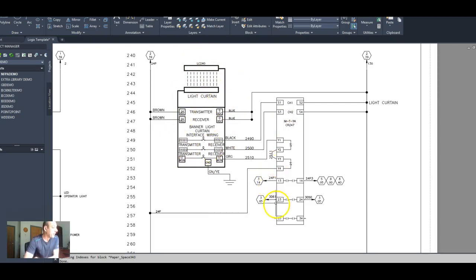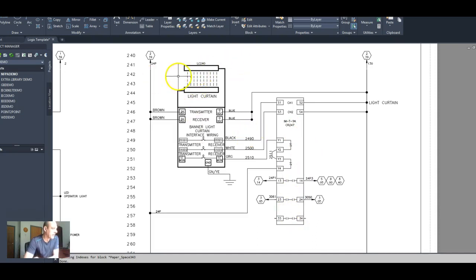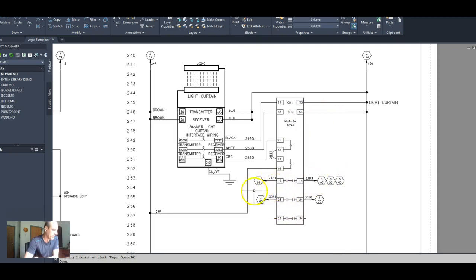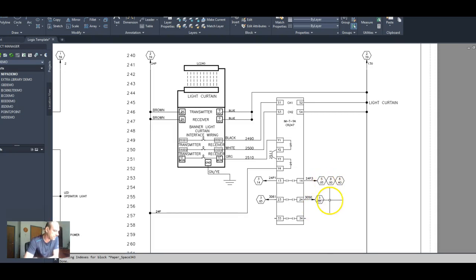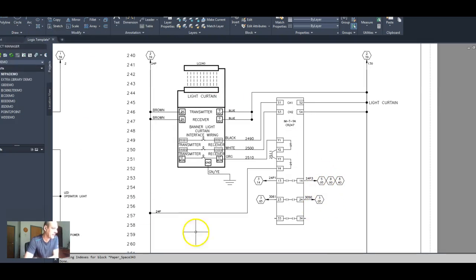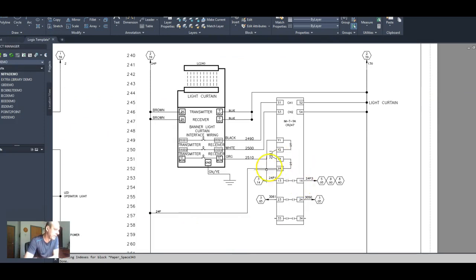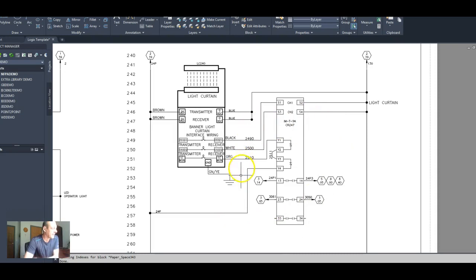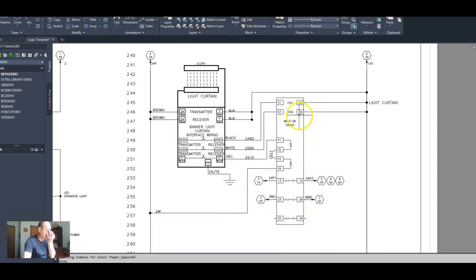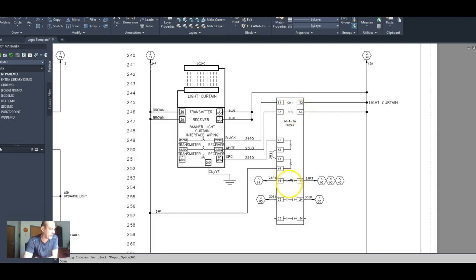We also have a safety relay right here. So if the light curtain gets interrupted, we drop our power out and then we prevent power from going to any other part of our machine. So for example, our 505. If this is energized, remember this print is in a de-energized state. So these are open when these two circuits are energized, these will close permitting power to flow, current to flow through the circuit.